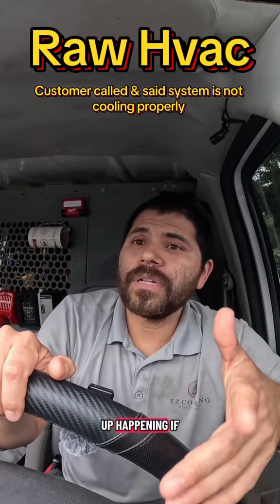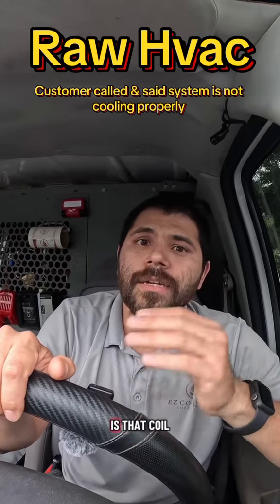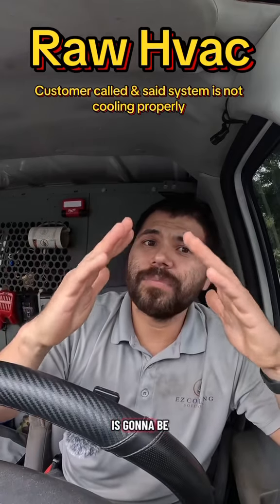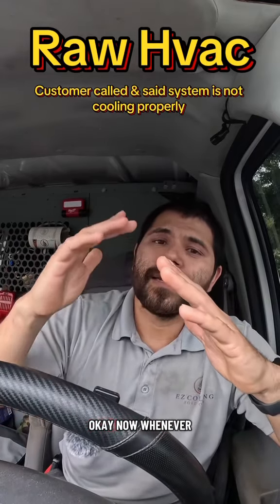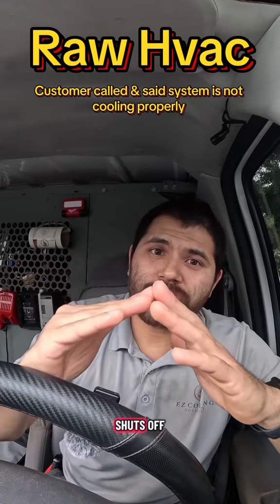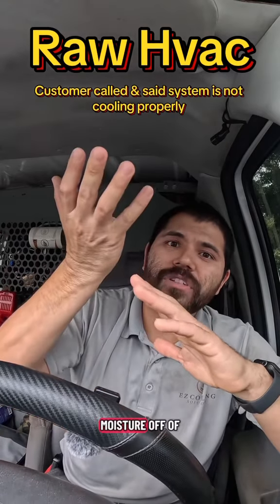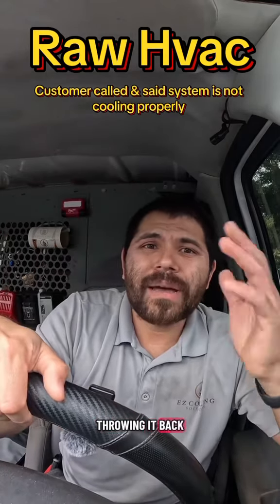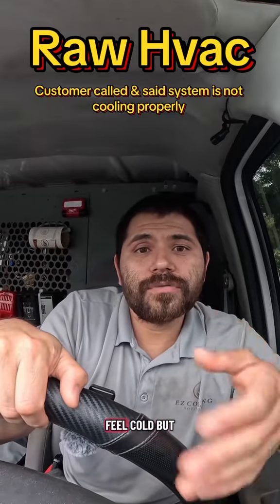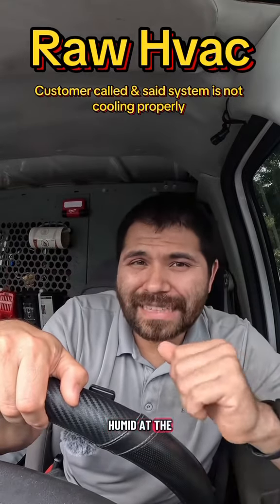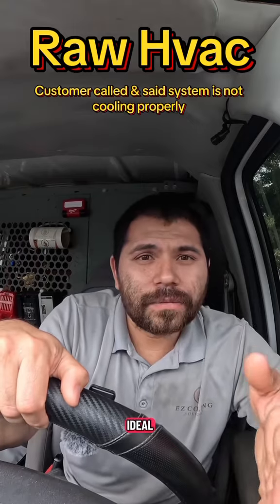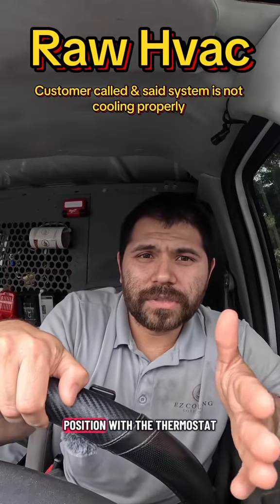Now, what happens if you leave the fan on the on position is that the coil ends up completely wet. Whenever the air conditioning shuts off, it's literally pulling all that moisture off the coil and throwing it back into the space, which makes it feel cold but humid at the same time, which isn't ideal. It's best to keep it on the auto position.